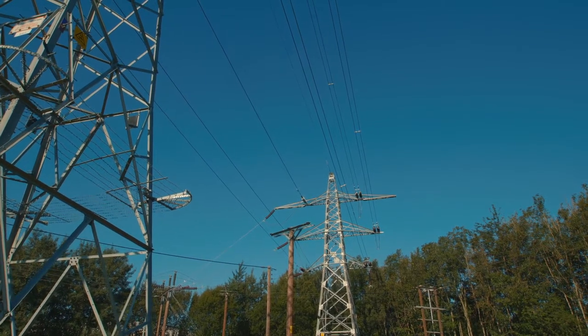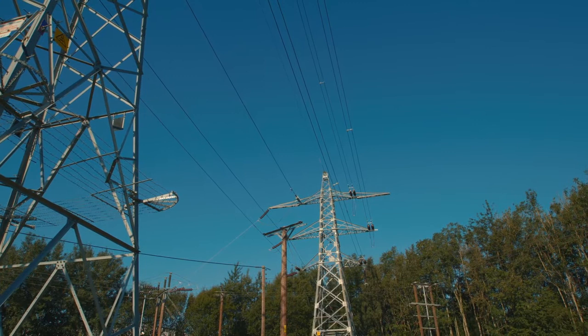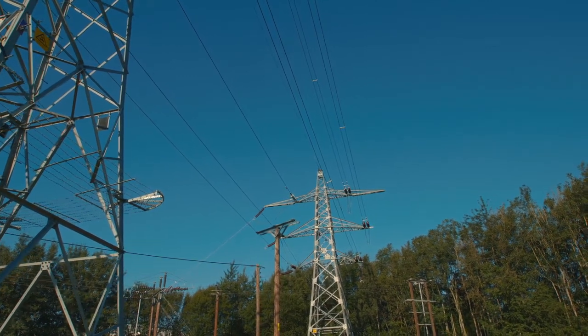There are also those faults that we call transient faults which don't cause protection devices to operate, and basically we rely on customers to phone in and say they're off supply, and from this, depending where those customers are, we can identify that a non-telemetry device may have operated on the network, say fuses, because we don't know whether fuses operate within the HV control room.